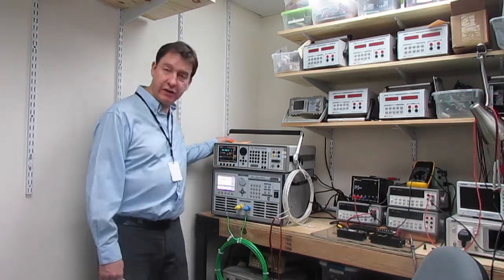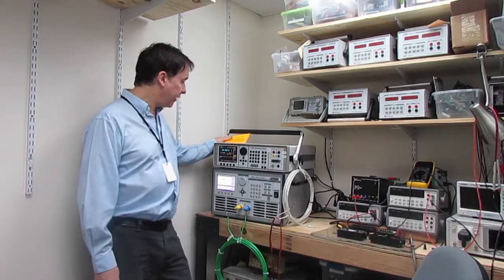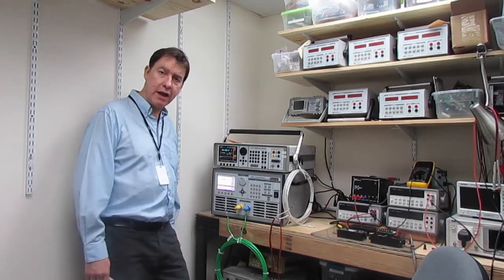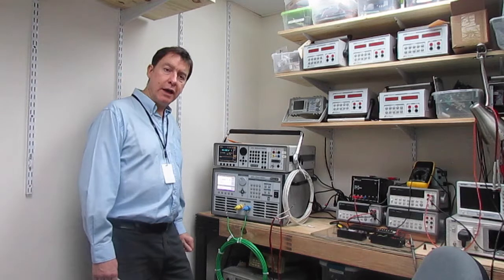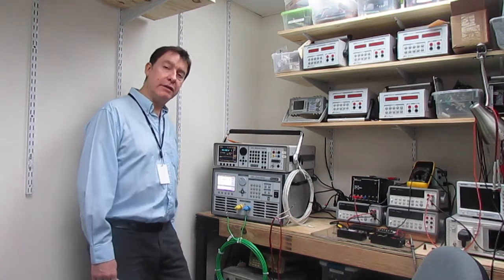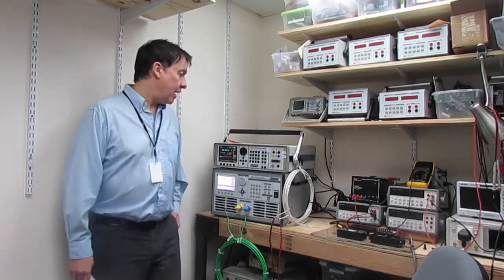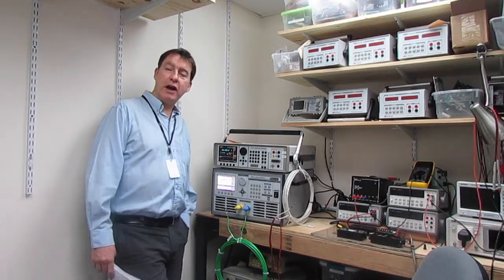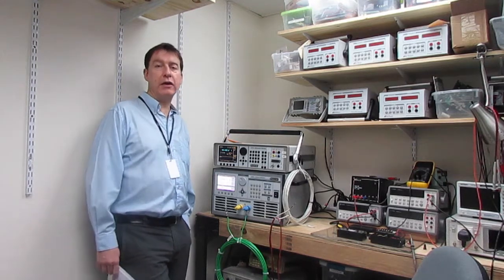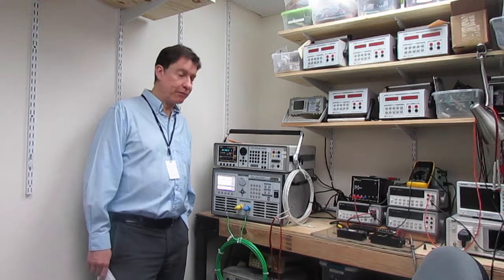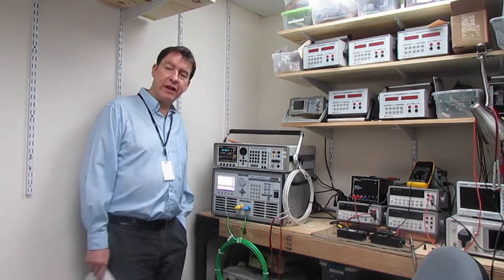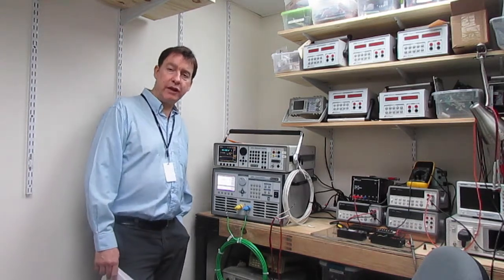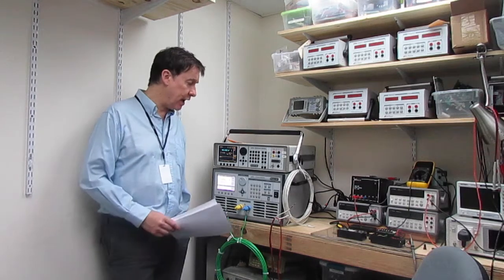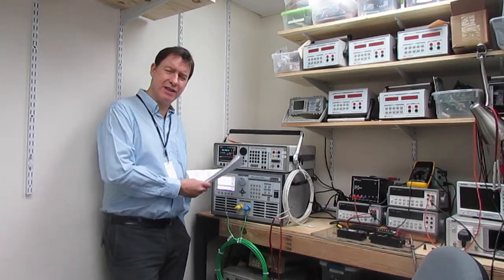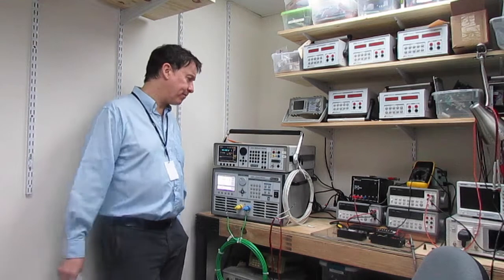I must stress that it is a working standard at Powertek, and this particular calibrator is sent away every year to an external accredited calibration facility. And that can be, for example, ISO 17025 or A2LA or Z540. In the UK we have them sent away for UKAS, so we use external laboratories to actually allow the traceable link and the accreditation of this calibrator.